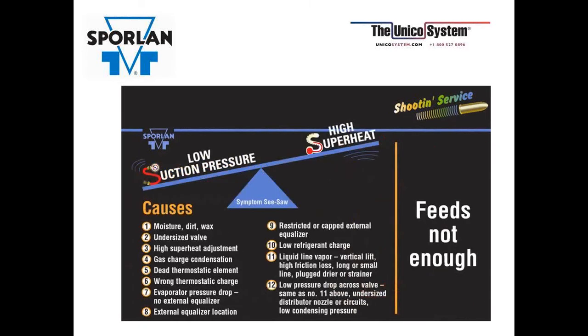I'm not going to read all these causes to you, and you don't have to write them all down. They can actually be found on your Sporlan PT card. So we're going to go to the first one, the feed's not enough. That's low suction pressure and high superheat. You took those readings, now you know I've got low suction and high superheat. I'm in a starved condition. Here are some of the issues that could be. Like I said, I'm not going to read them all, but the first one, moisture, dirt, wax, pops right out at you. If the valve's sticking, it can't open and close, then it's going to have a problem. Could be the wrong element charge.